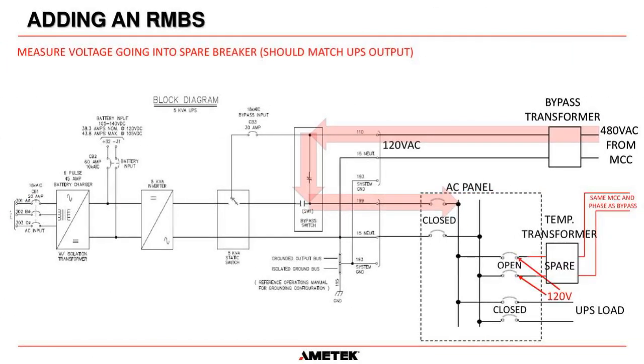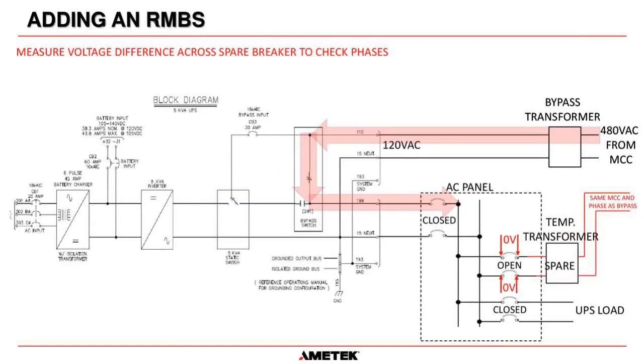So now what we need to do is make sure that we have 120 volts on this side of the breaker, on the back feed side of the breaker. Because we're going to have 120 volts on this side coming from the bypass output here, we need to make sure with a Fluke or any other multimeter that we measure phase to phase on the same phase across that breaker. We're trying to make sure there is no voltage difference between those two points, because they should be nearly identical, and obviously do it on the neutral as well.